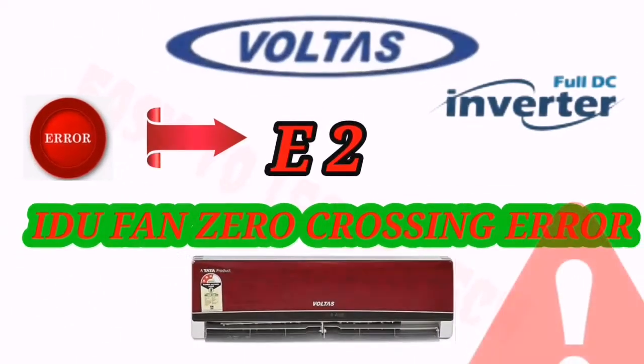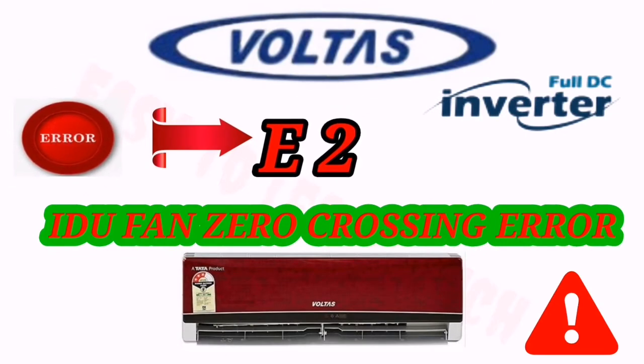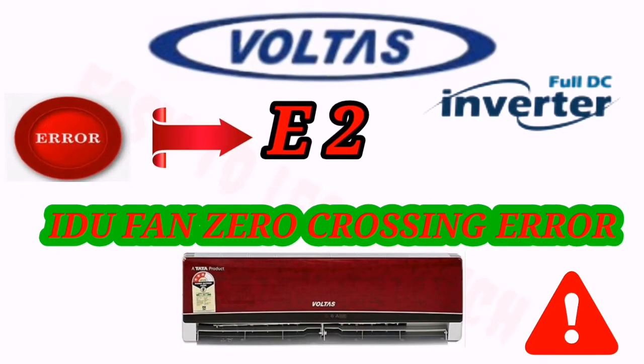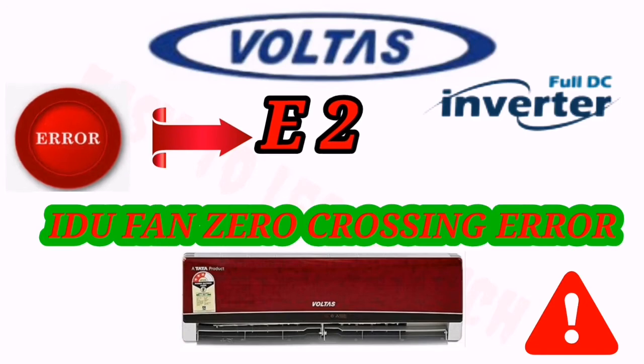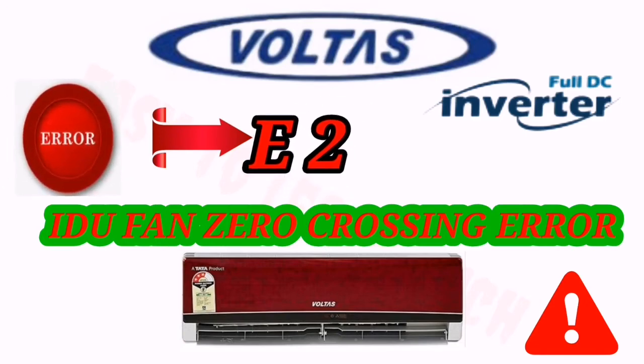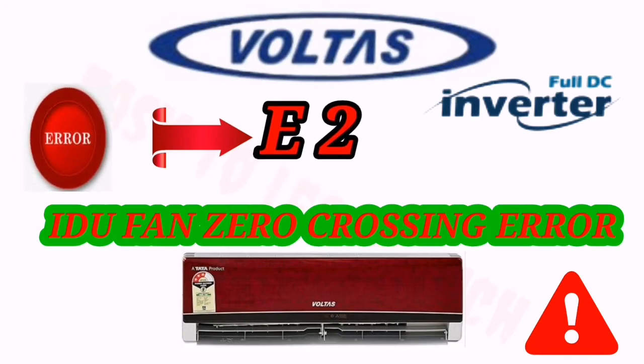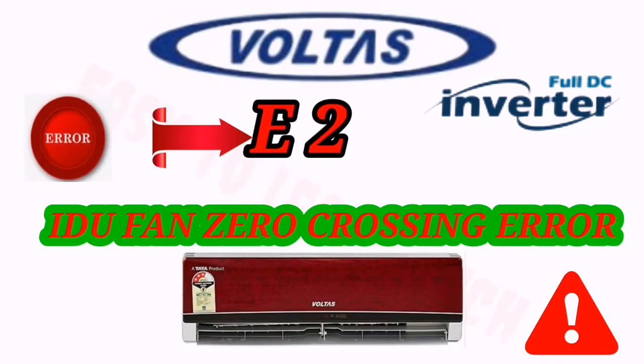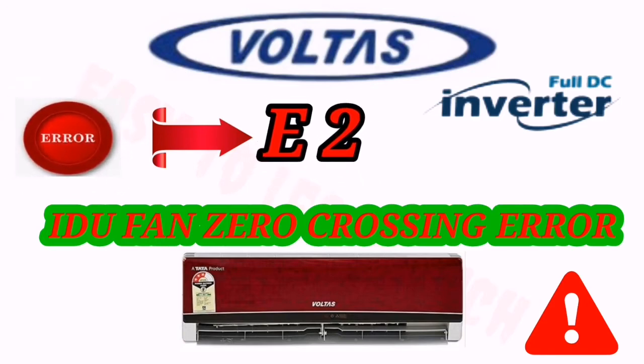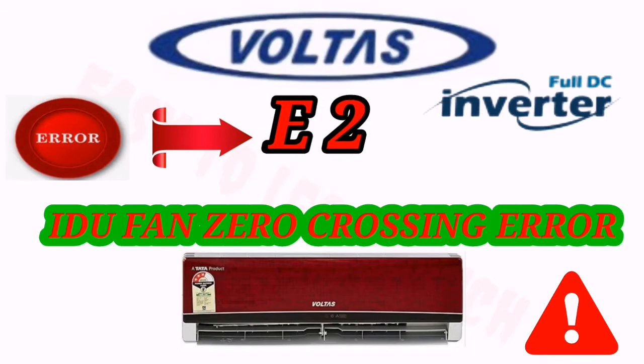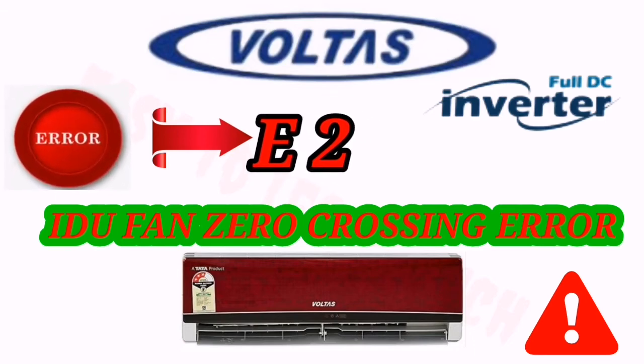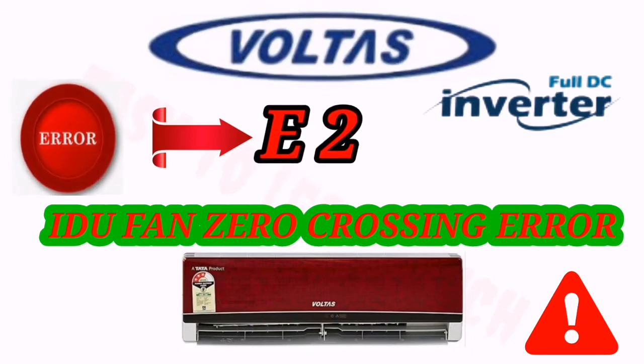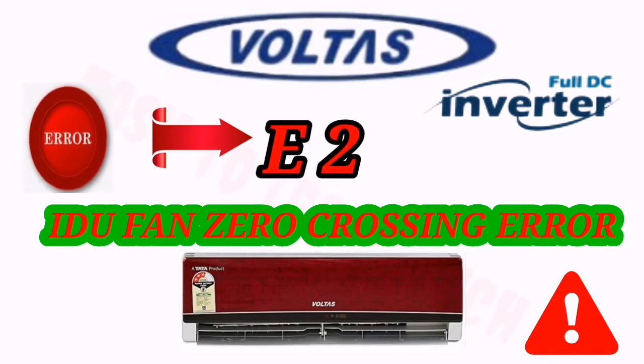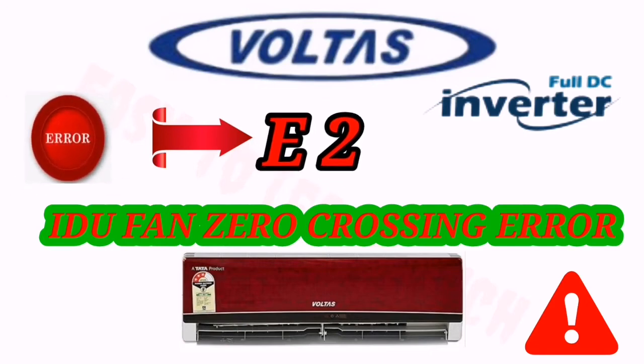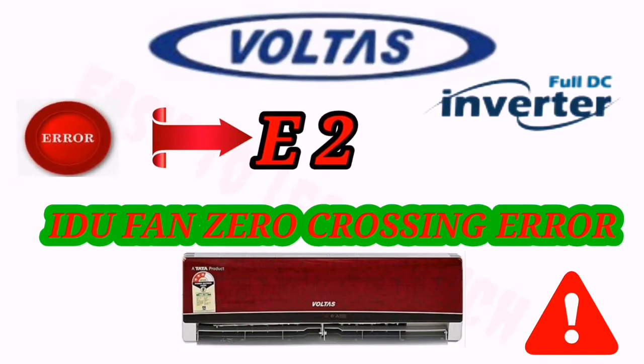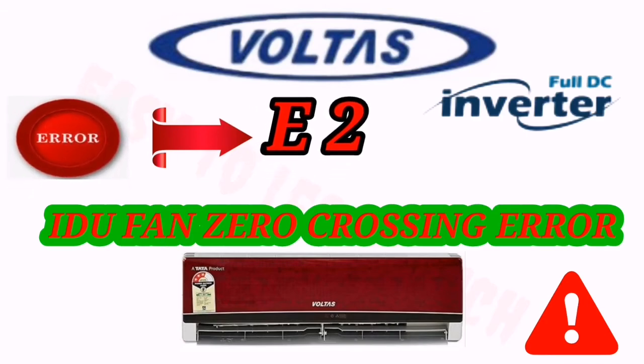Let's see the next error code. When you see E2 in your display, it means indoor fan zero crossing detection malfunctioning. This error occurs when one component of the fan zero crossing detection circuit is not working or not okay. Mostly this malfunction occurs due to broken parts on the indoor PCB, either from falling down or sometimes when we install the unit, it crashes with the swing motor or the fiber parts. At that time this error occurs.